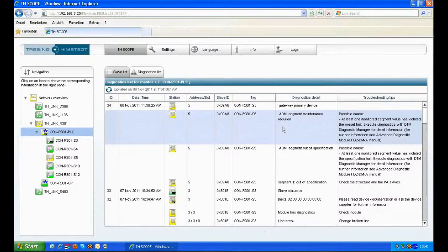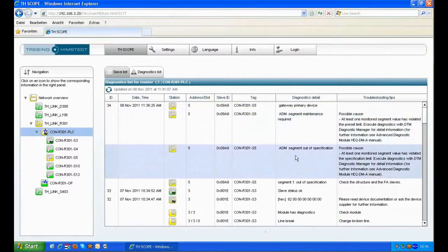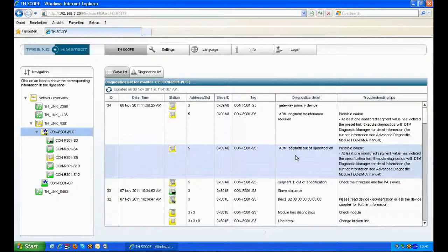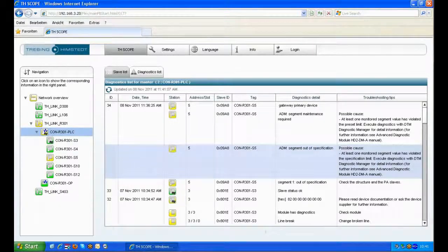Going back to the diagnostic list we see the diagnostic details: ADM segment maintenance required and ADM segment out of specification. With this information we can go further to the FDT application to solve the problem in detail.